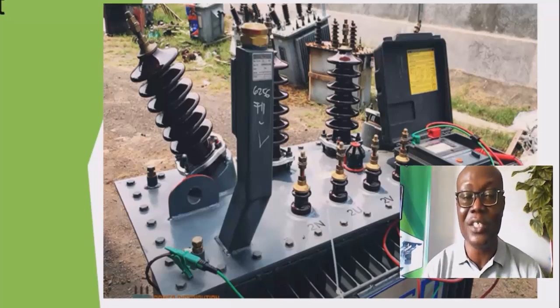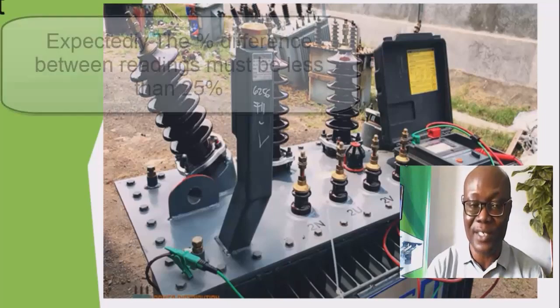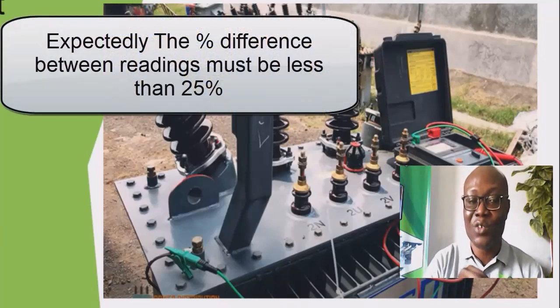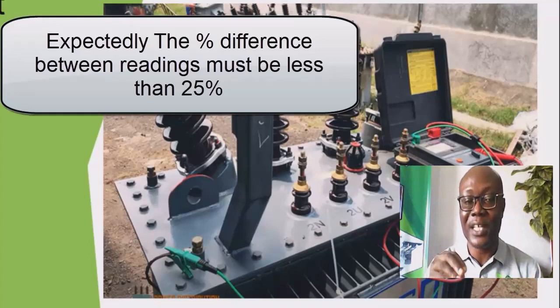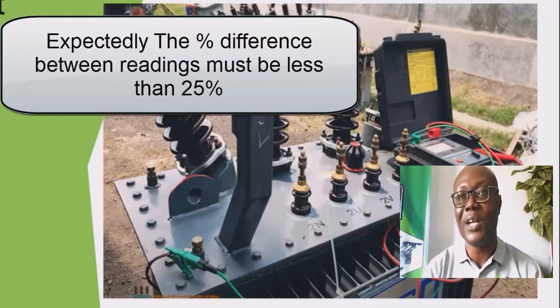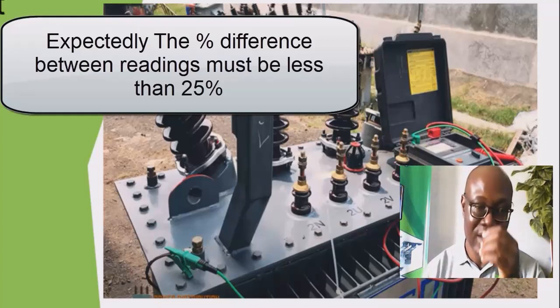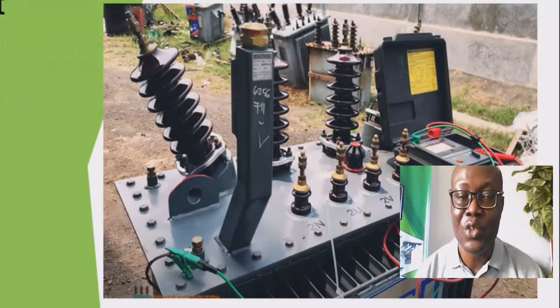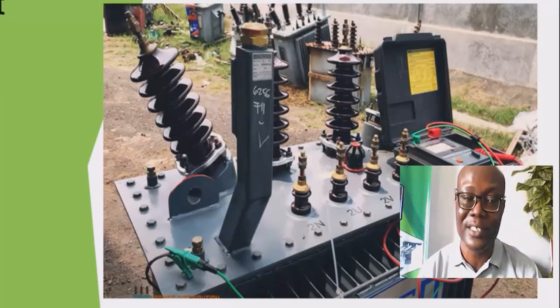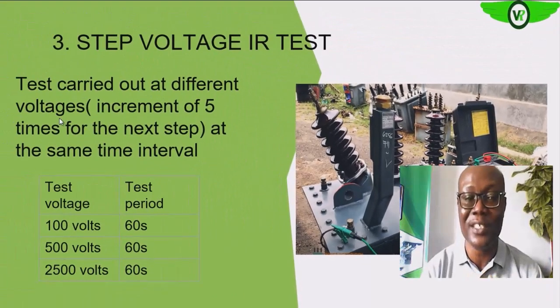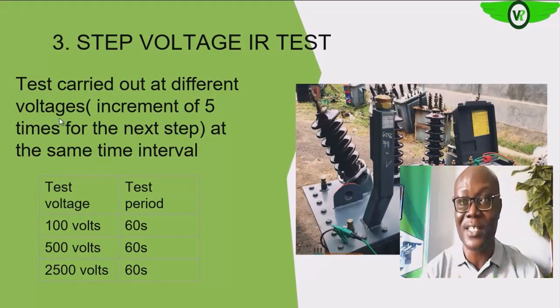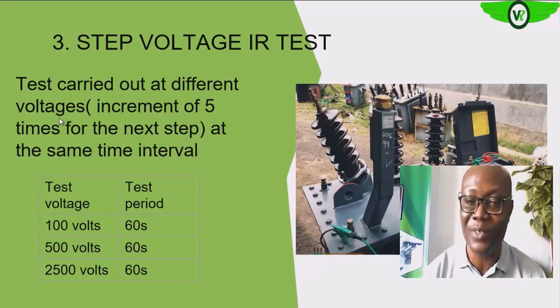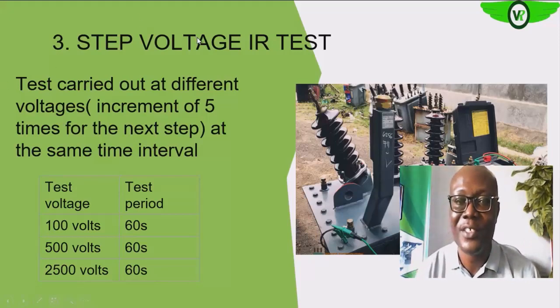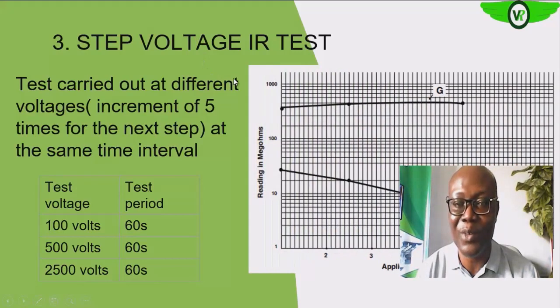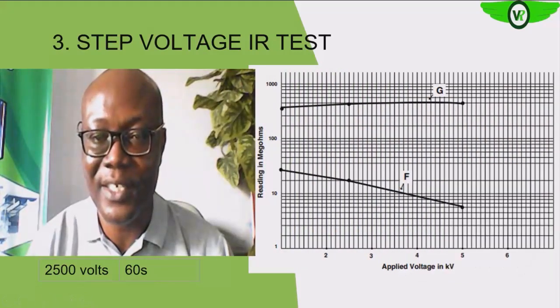Expectedly, in the IR reading, you are not supposed to have more than 25% difference between the IR reading at 100 volts and the IR reading at 500 volts, and also between 500 and 2500. So once you have that marked difference in the IR reading, maybe expectedly as you are increasing the voltage it drops, but if it drops more than that 25%, of course, you will know that there is a problem developing already.